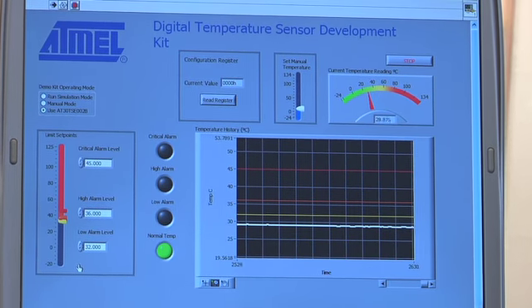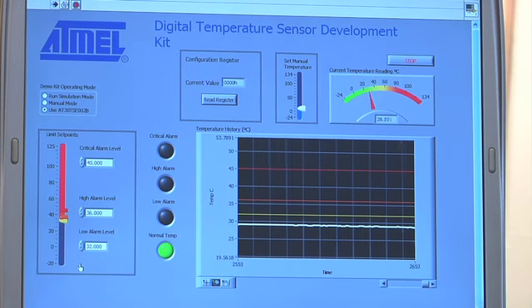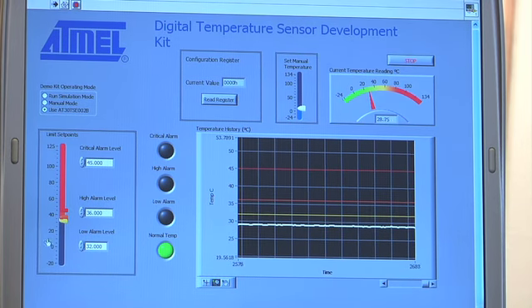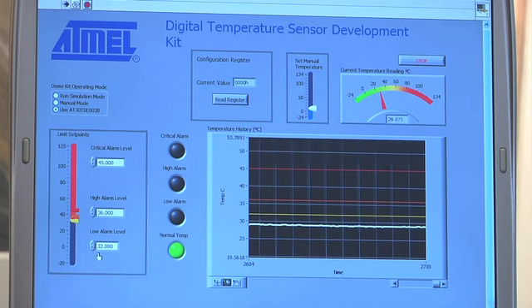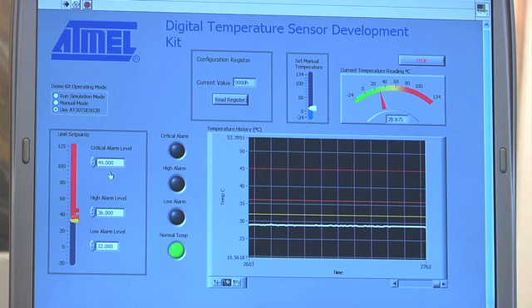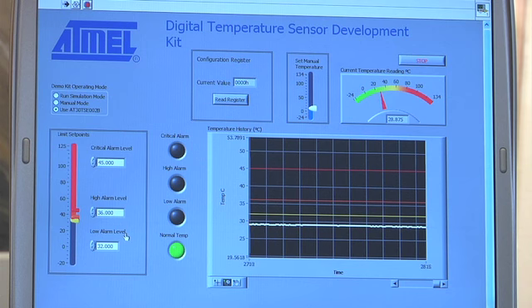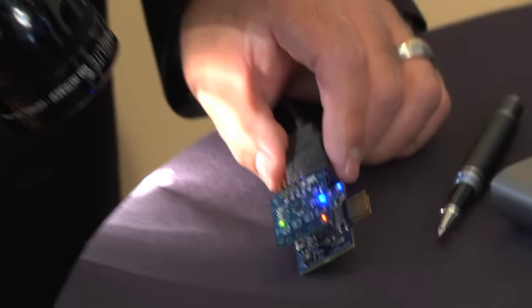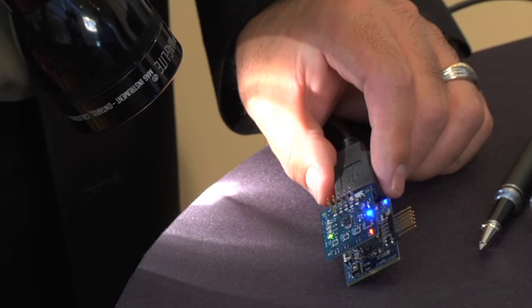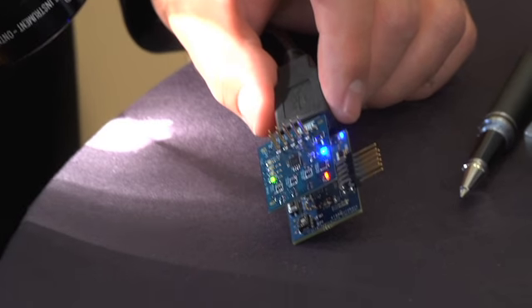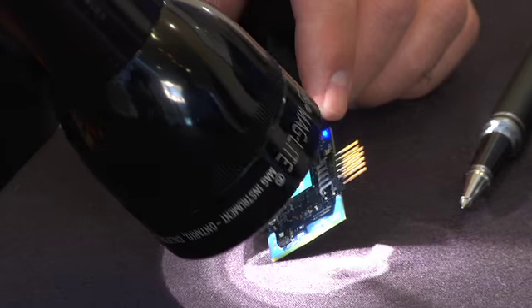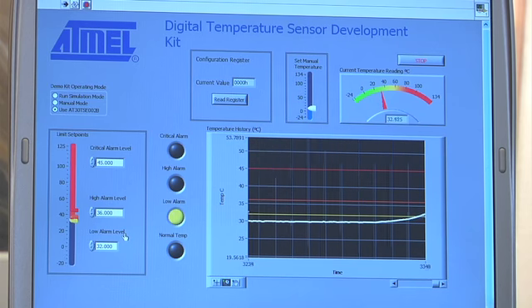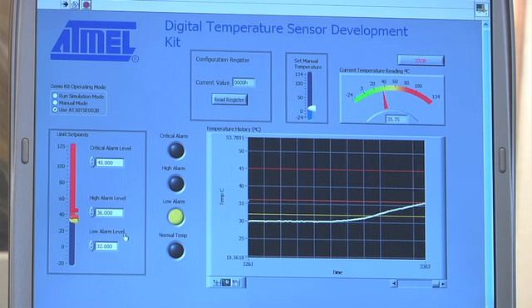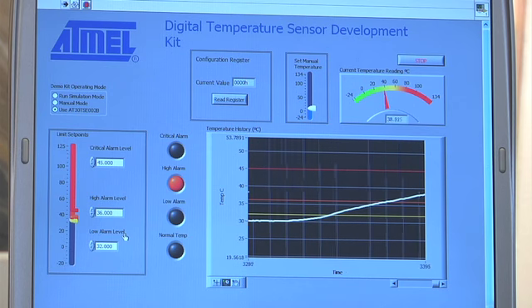So I'd like to actually go ahead and show you this device in action. I've already preset the temperature limits. I've got the low alarm limit set at 32 degrees C, the high alarm at 36 degrees C, and the critical alarm at 45 degrees C. And again, it's currently about 29 degrees C inside this building here. So I'm going to use a flashlight where I've removed the lens cover to generate a heat source to heat up the temperature sensor device. And so I'm going to place this really close to the device, and you can see the white line there on the graph begin to rise as the temperature increases.